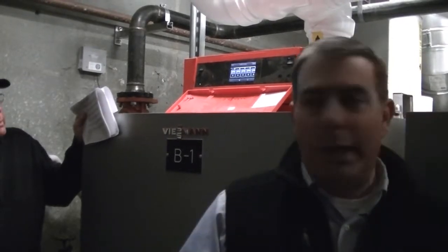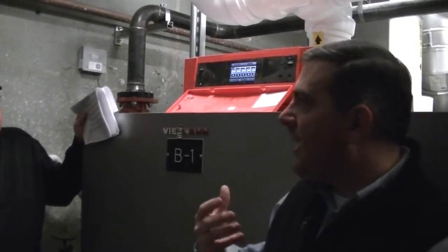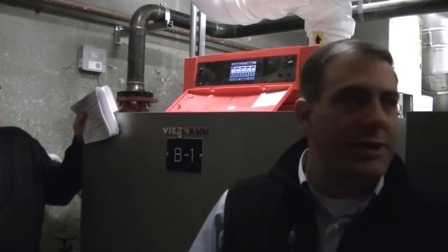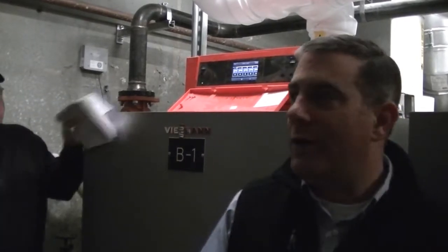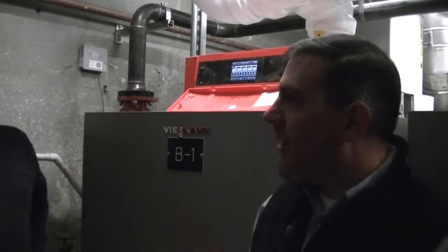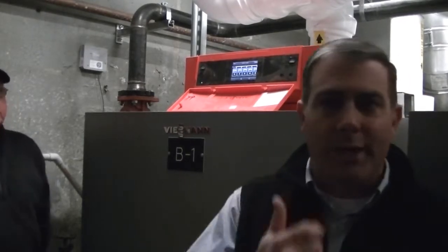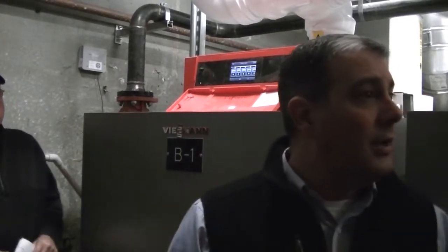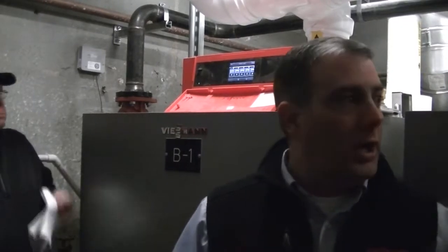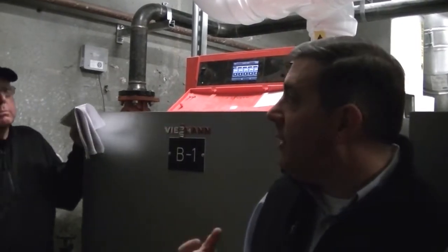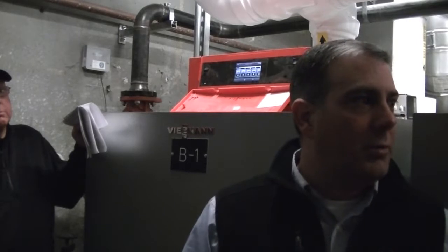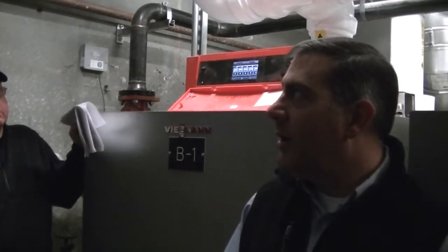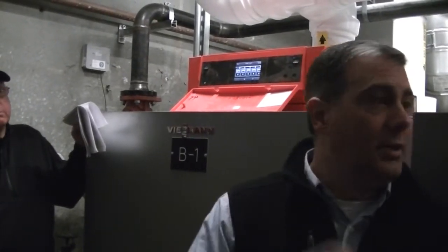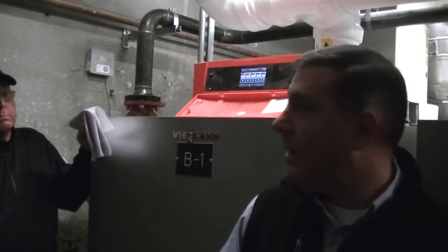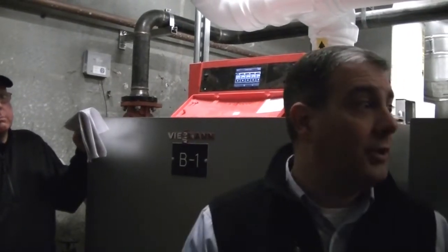So what I would ask you all to do, if you're down here at that time when you see a fault, before you hit a reset button, before you turn something on or off, either take a mental note of what that fault is, write it down, or take a picture with your smartphone, and just save that. So at least when you call Tom or call us or call somebody to figure out what the problem is, we have a starting point and we can diagnose the problem a little bit better. So before you hit the reset button on anything, at least take a note of what that lockout failure or what that fault alarm is.